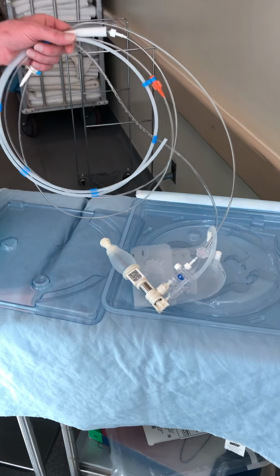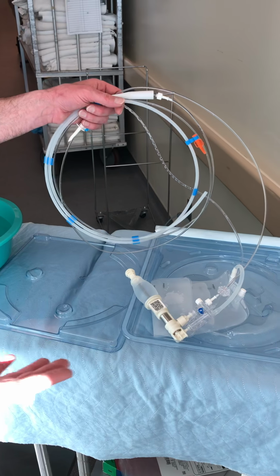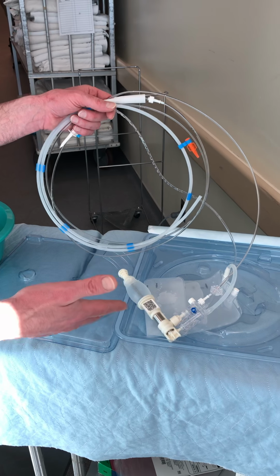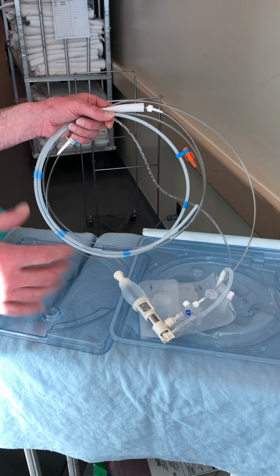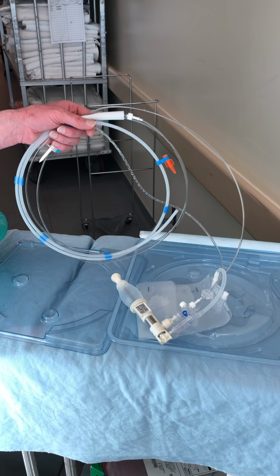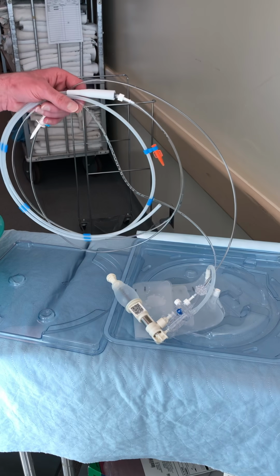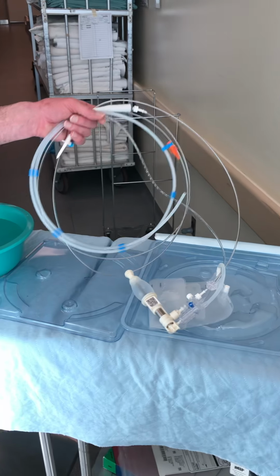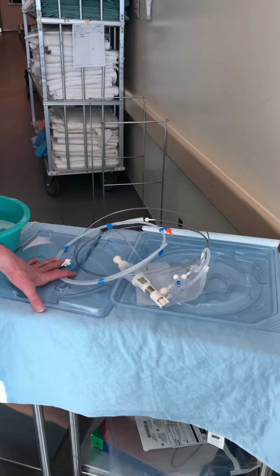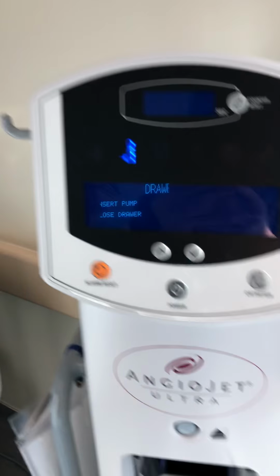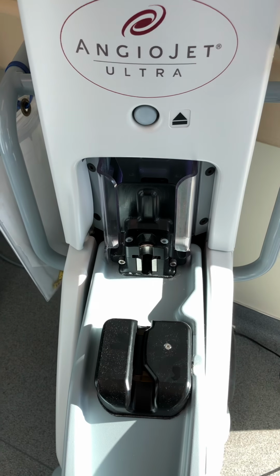The older versions of this had two components: the tubing and waste set, and the catheter. They came separately. This is all contained in one unit now, so there's very little that you need to do with it. Once you see the power on the machine has been turned on, this door will open automatically. And it's going to tell you on the screen exactly what you need to do.